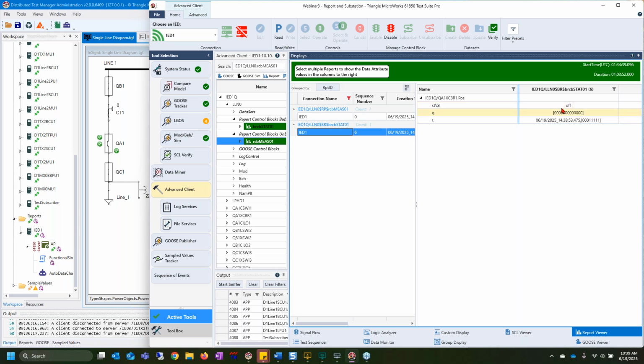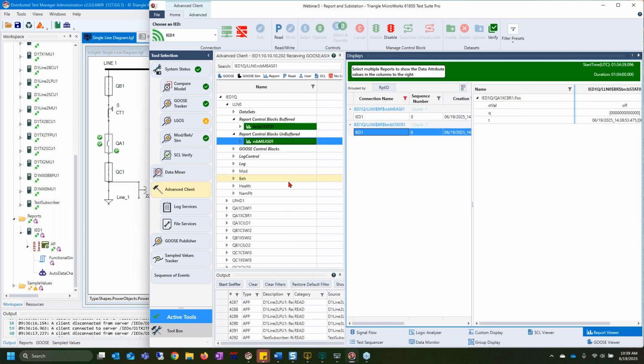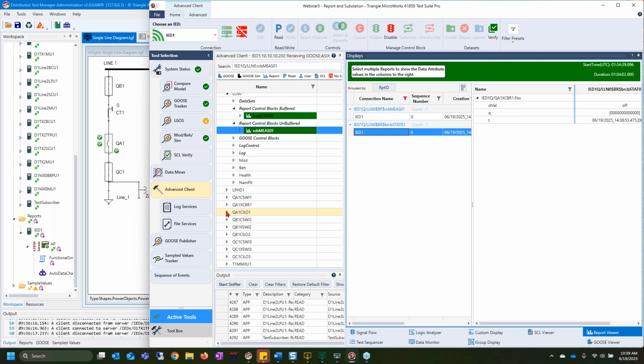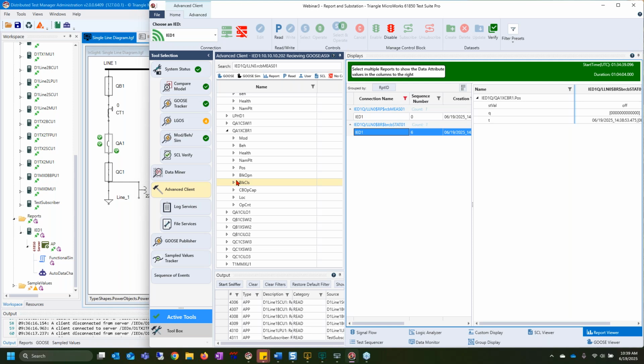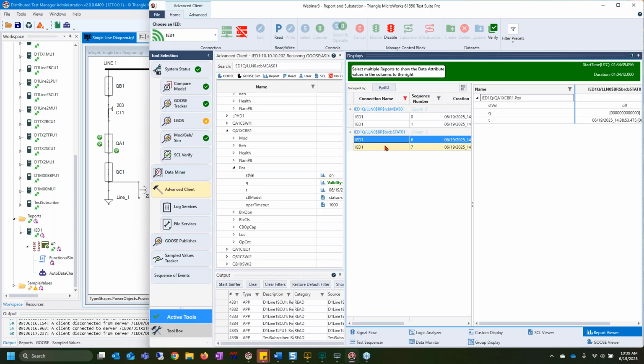So this specific report shows that the status value of the position has switched to off. Since we did receive this report, that allows us to keep the model up to date. I don't need to go down and do a poll. It is now getting this by report. And now if I go and close this again, sure enough, we'll see another report come across.